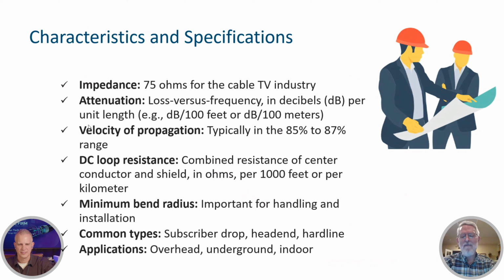That's typically in the 85% to 87% range. There are some exceptions to that. The old MC squared cable was up in the 92% range for velocity of propagation. And if any of you have used communications cables, mostly 50 ohm impedance cables, but also early RG59 type cables that had what's called a solid poly dielectric or solid polyethylene, that's 66% velocity of propagation. And then the so-called power feeder cable is up around 83%. And I'll show some examples of at least a couple of these a little bit later on.